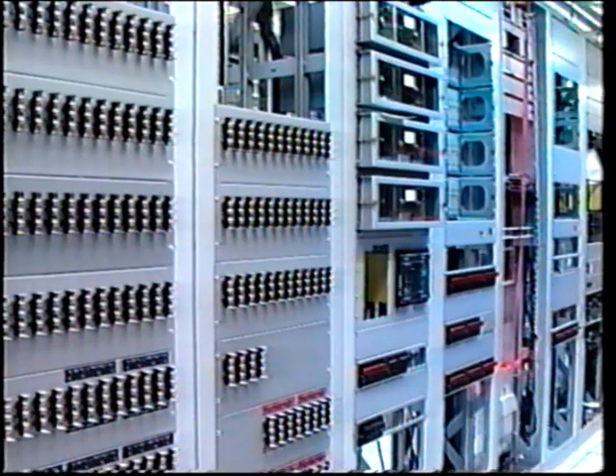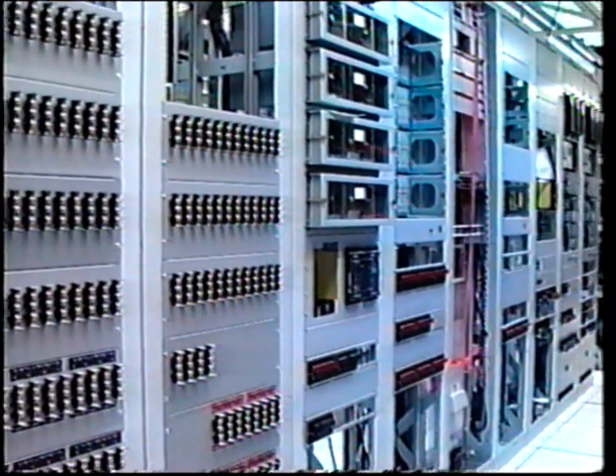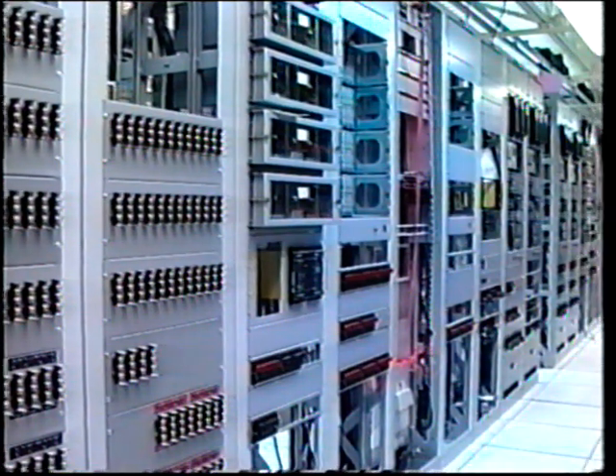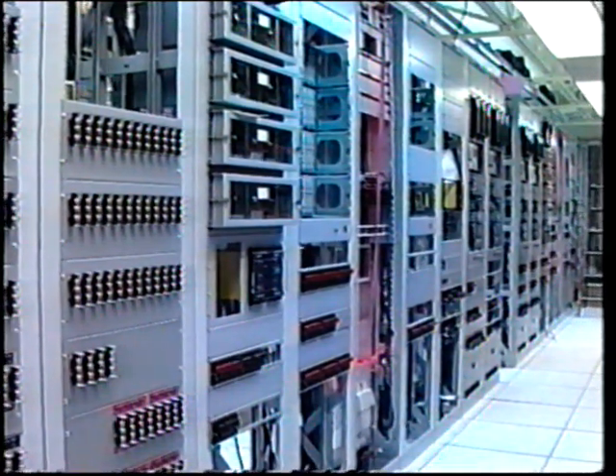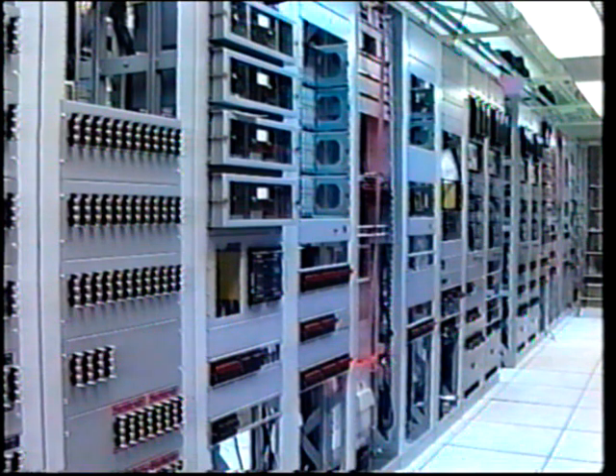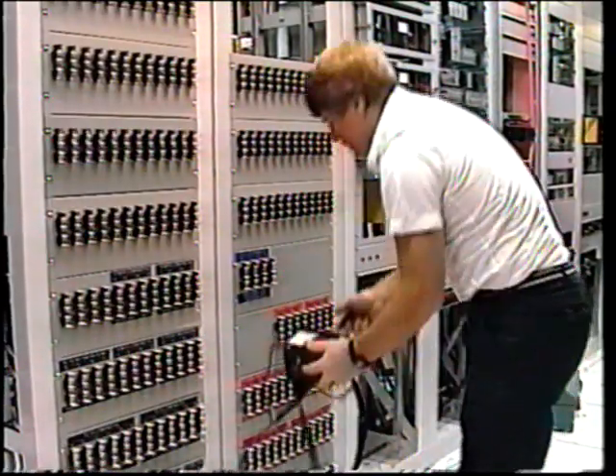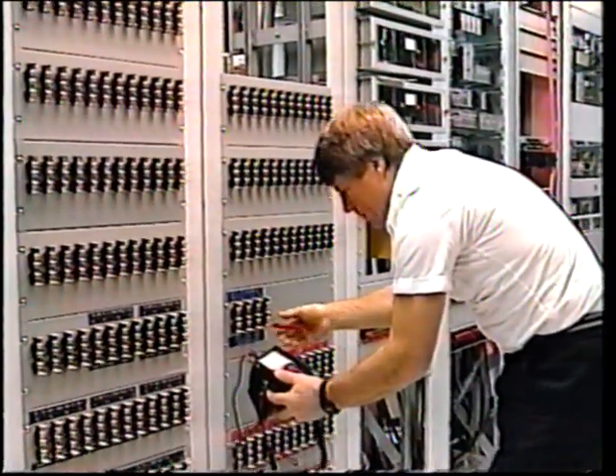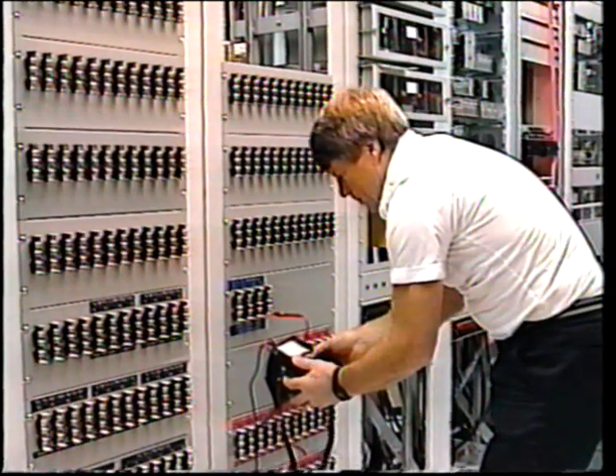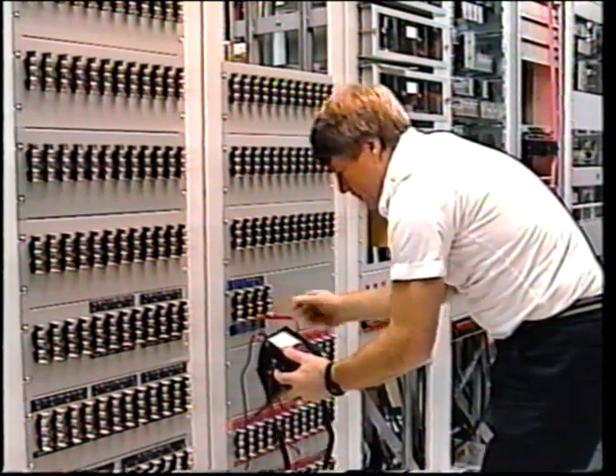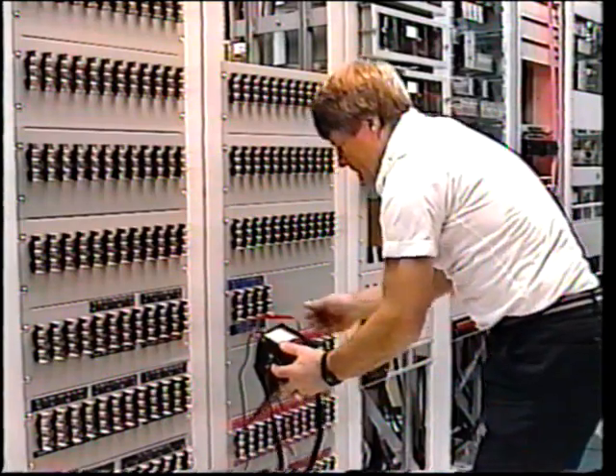We must also check that components mounted on the panel by the manufacturer coincide with those shown on the elementary diagrams. This includes such items as resistors, capacitors, diodes, transformers, and various switches. This checking out of the wiring may well be tedious, but it is clearly necessary in order to avoid problems such as discussed in our earlier examples. After the wiring checks have been completed successfully, we're ready to look more closely at the protection scheme.